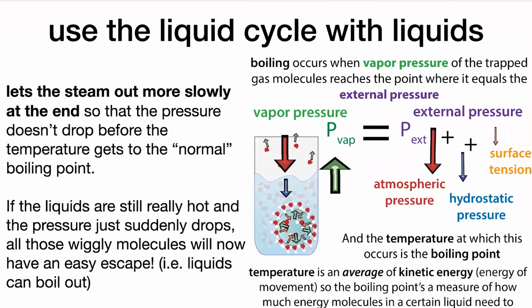To really prevent overflowing, make sure you're using a liquid cycle. At the end of the run, the autoclave lowers the pressure. If you lower the pressure too quickly, those molecules still have that high energy and high temperature, above the normal boiling point.